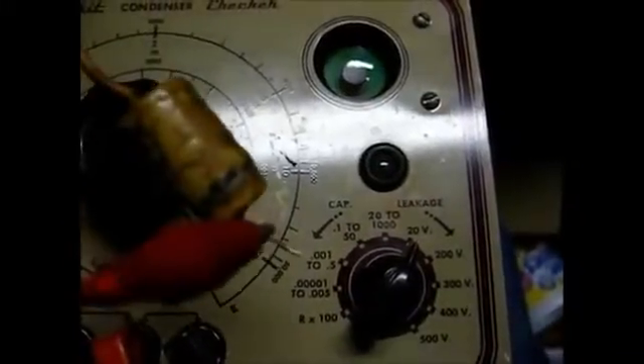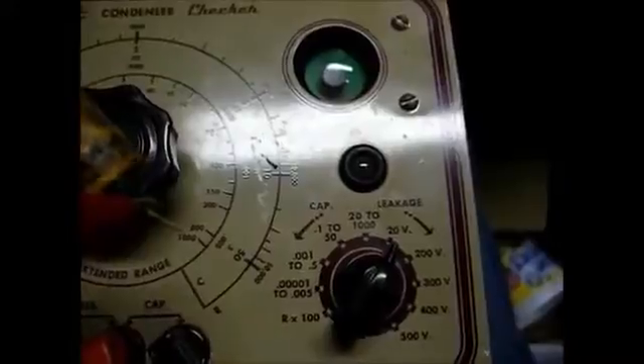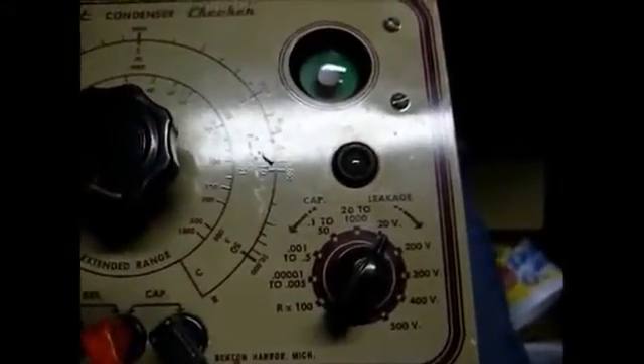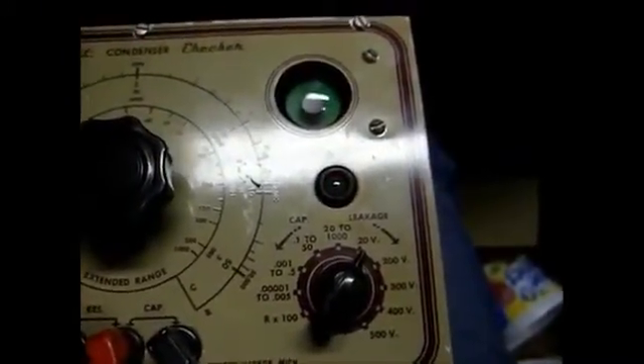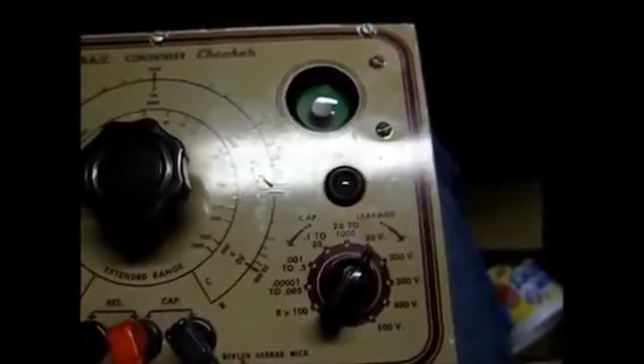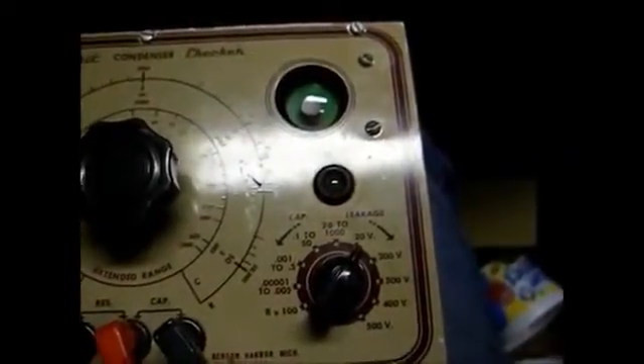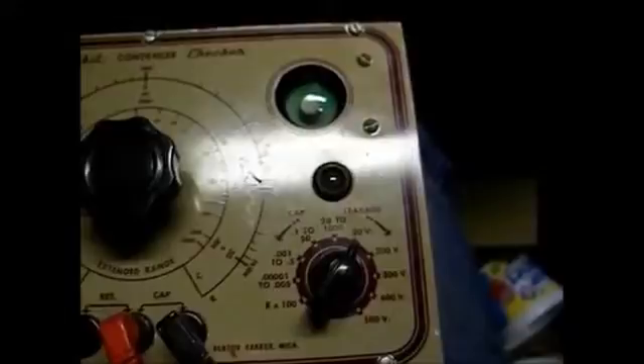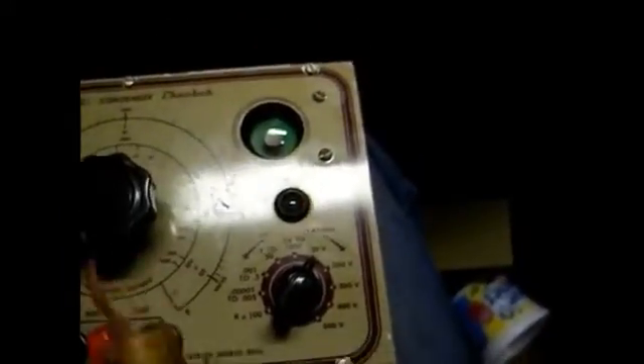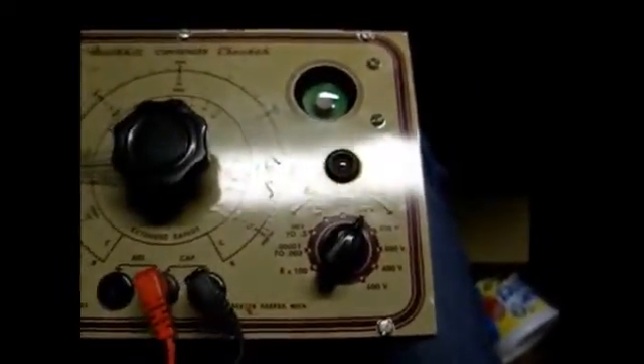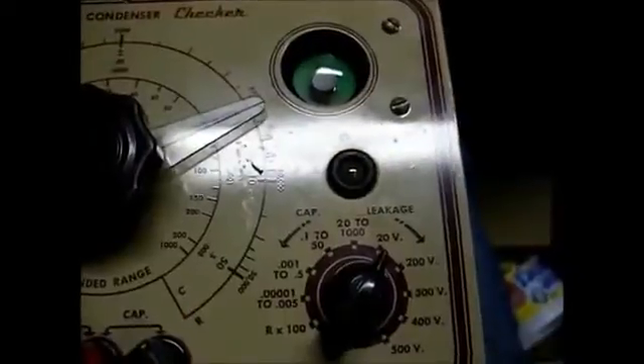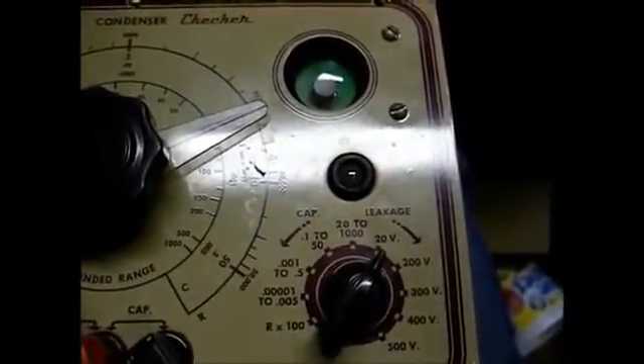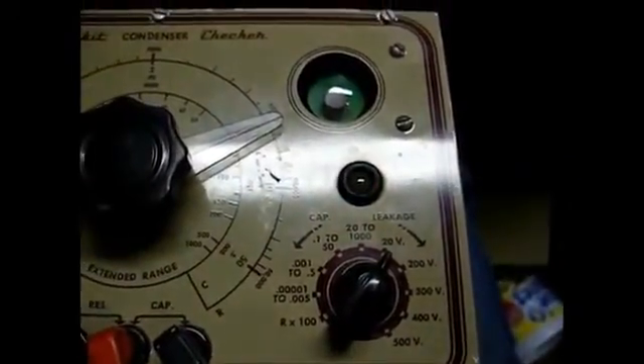Here's the 0.33 microfarad capacitor. As you can tell by the flashing light, it's leaking a little bit. Since this is rated at only 100 volts, I'm not going to advance the leakage voltage test any higher, there's no need to. And here's the 0.05 — it's leaking a little worse than the last one.